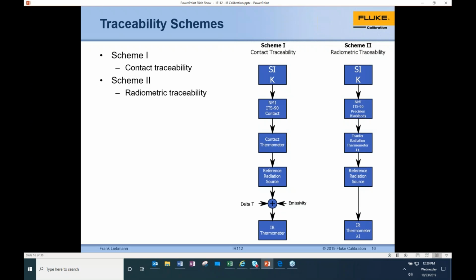In scheme 2, we're using pure radiometrics. The NMI is going to test our transfer standard gun. We're going to use that gun as the standard to calibrate our radiation source. And then we're going to use that radiation source, which in this case would be the 4180X units, to calibrate our infrared guns.